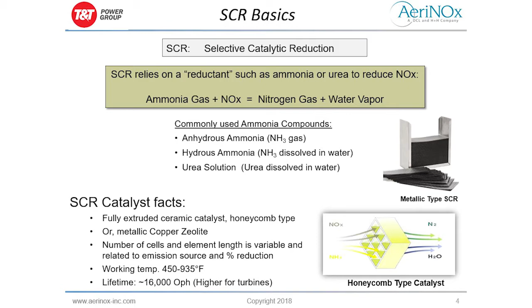The most prevalent, the most common in this industry—certainly in power gen and CHP when driving smaller recips, 1, 2, 3 megawatt type applications—is urea. It's a fertilizer. We spill it on the ground, means nothing. It dries, forms a white powder, wash it off with a hose. It's considered a non-hazardous material by the EPA.